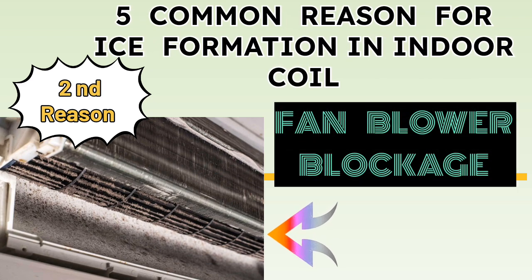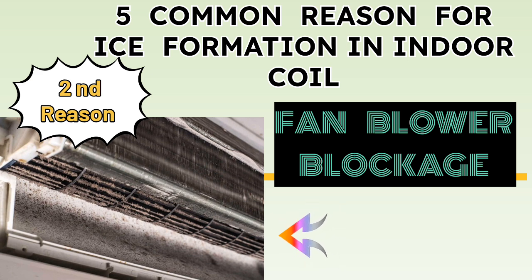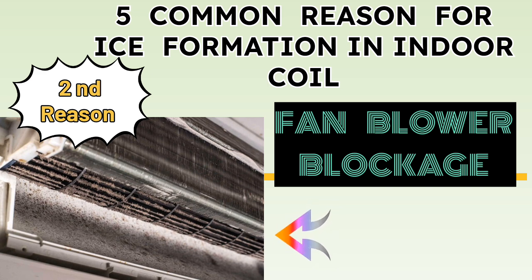The second reason for the ice formation in our indoor unit is the fan blower. If our fan blower is blocked or totally dirty and the airflow is low during the running of the air conditioning, the evaporator will make ice and you will get water leakage and low cooling. To avoid this, clean the blower frequently and you will get proper cooling with no ice formation.